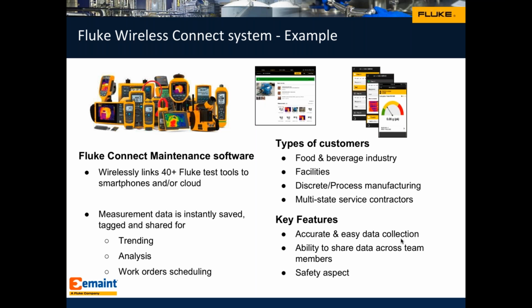An example is I had recently a customer who mentioned to me, when the train comes out in the yard, we need to actually take a thermal picture of the bearings. And I was asking them exactly what they were doing with those pictures. And they said, well, we are here downtown, and the engineering team is about 15 miles away. So if I have the ability to take thermal imagery and upload it onto the cloud, it can be shared within minutes with the engineering team, and they can look at the pictures and determine if we need to actually replace the bearing or not.